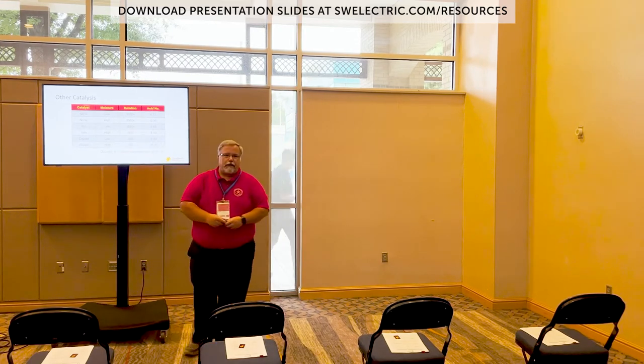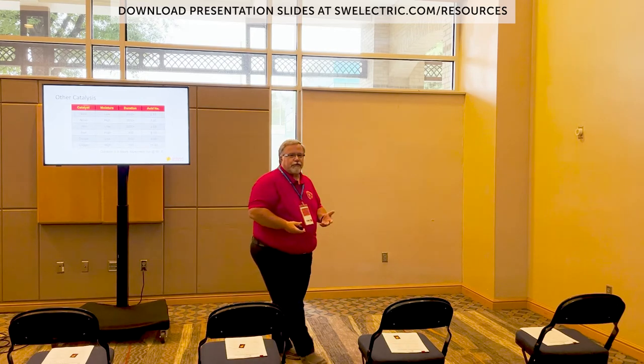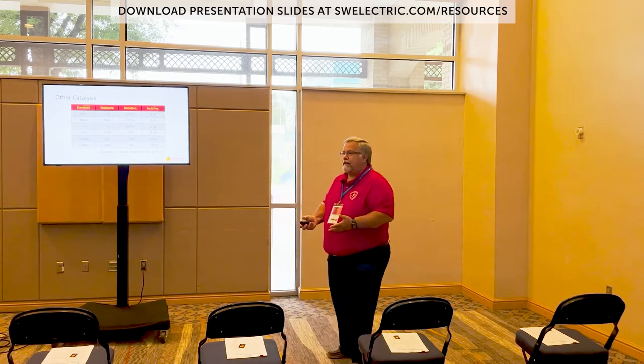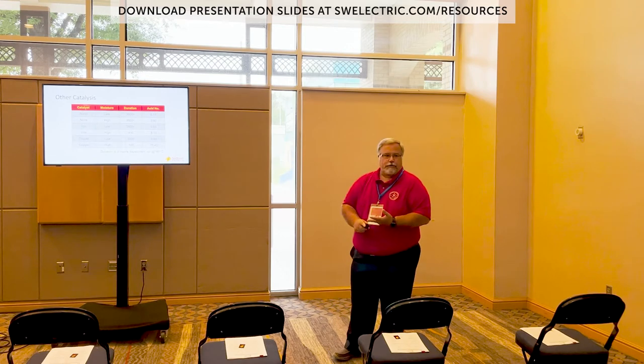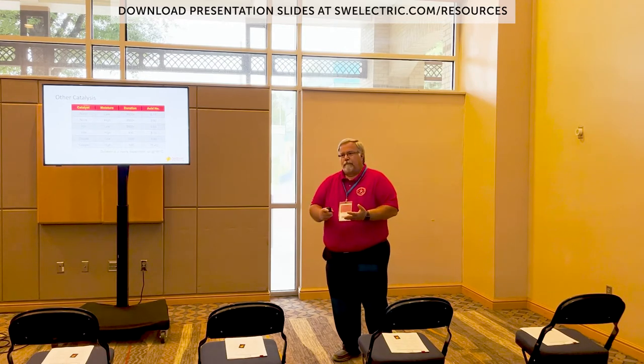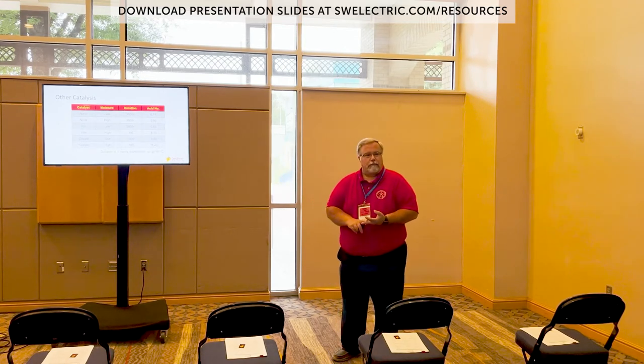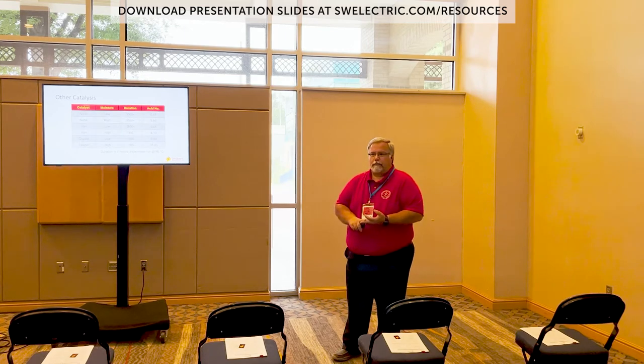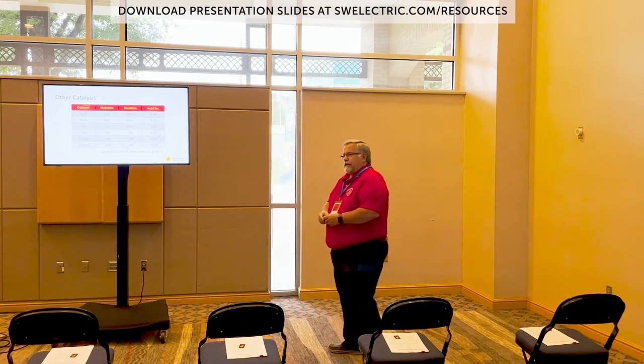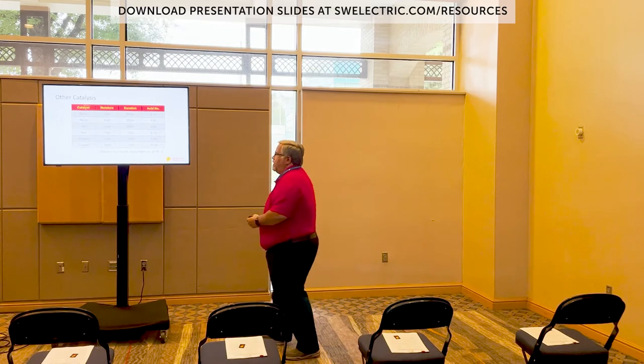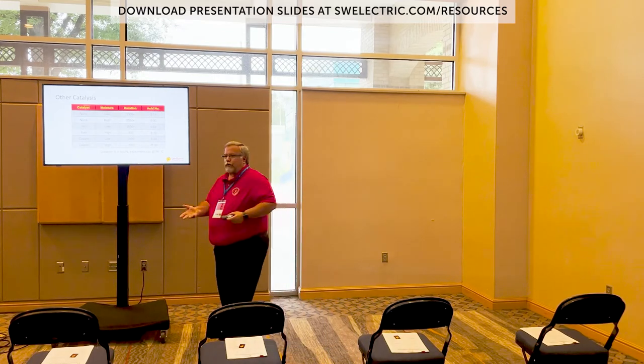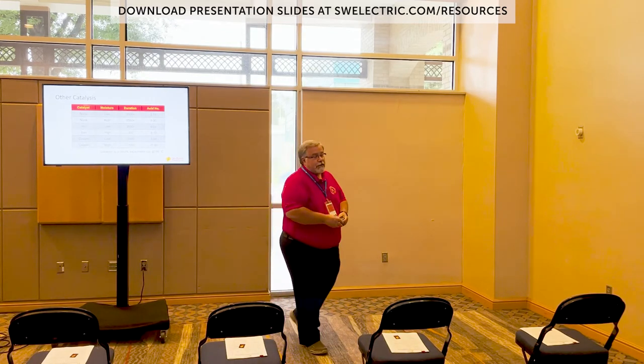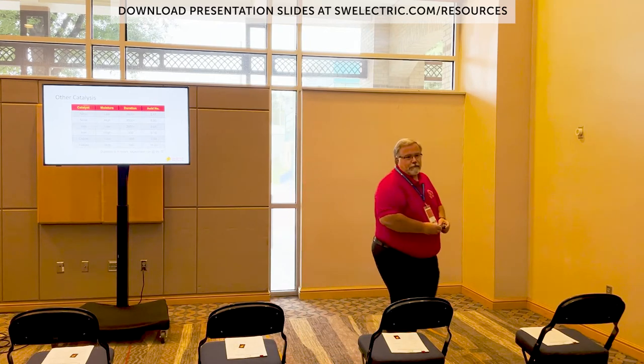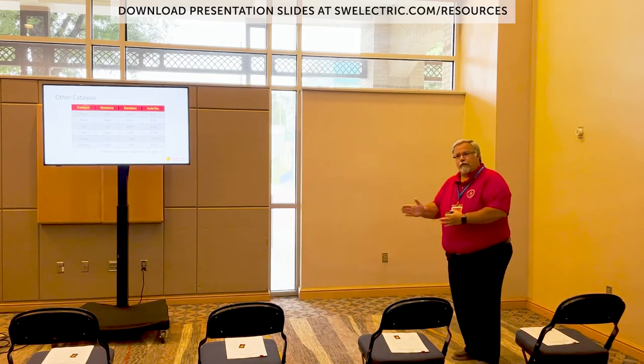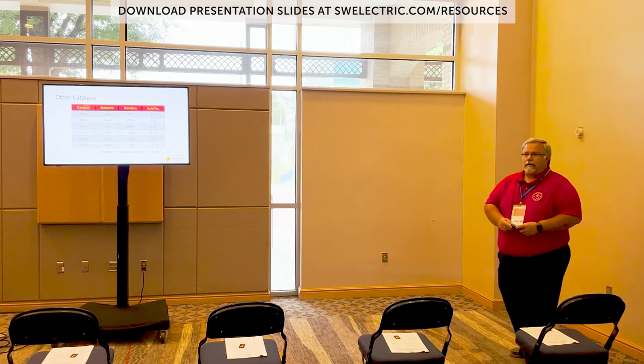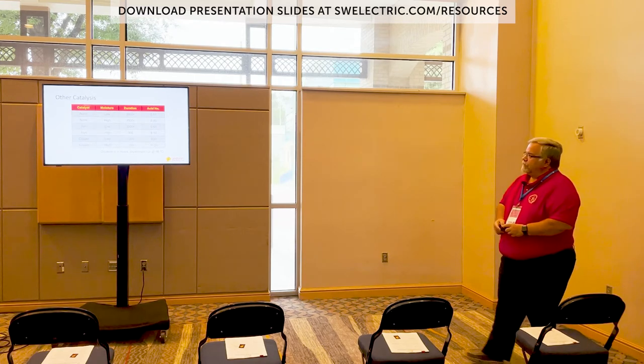But that's not really a transformer. We have things inside our transformers that are catalysts that we can't do anything about. Iron, you have core steel, copper or aluminum, one of the two, as your winding material. And there's nothing we can do about that. That's what's inside the transformer. That's how it's made. Now, during World War II, believe it or not, there were some silver wound transformers, but the government got those back real fast after World War II, because they wanted their silver back.